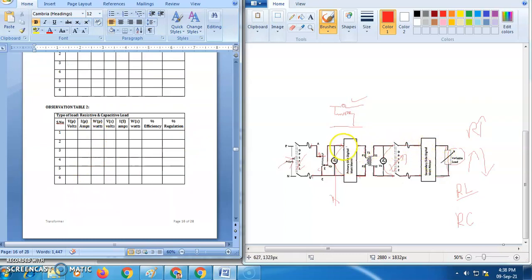On the primary side, whatever the rated current is flowing, up to that level you can record. So one thing you need to keep in your mind, using these digital wattmeters, you can take the ammeter value, current value, as well as the power input value, both from the same meters. On the secondary side also, you can record the ammeter reading as well as the input and output power readings, right?